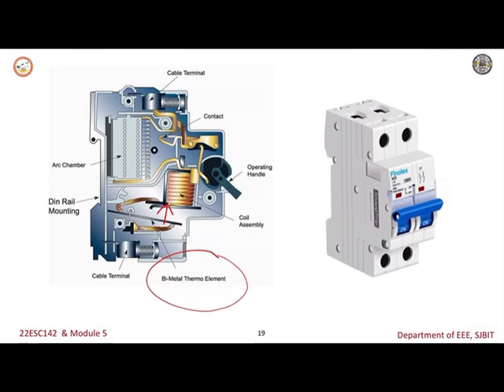Whenever it deflects, this circuit will open. Whenever the deflection of the bimetallic strip happens, it will release the latch. The latch causes the MCB to turn off by stopping the flow of current in the circuit. So this is how your MCB will work. Whenever high current or short circuit current flows through it, the bimetallic strip gets heated and deflects by bending. So it will be connected to a latch.